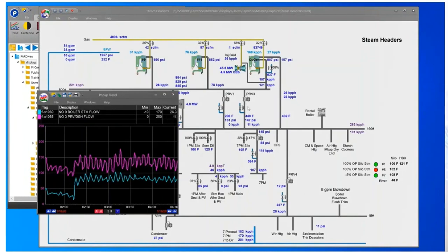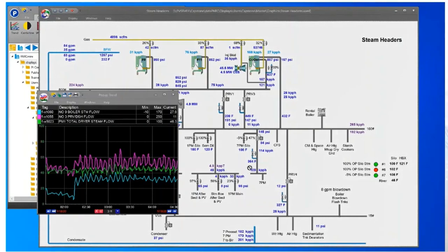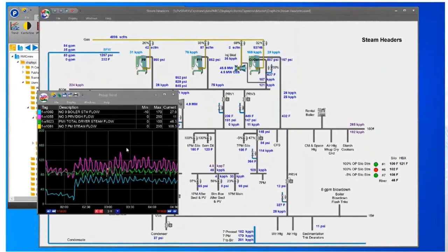So now the next question is, is it the controller itself that is causing the swinging, tuning, or is it some flows down below? Are they swinging that header so that it's pulling more or less steam? So we checked all of the flows except for these 2, and they were okay. But the 46,000 pound there, I'm going to drag that guy over, and I'm going to drag the 109,000. Those 2 look like they might have some variability.